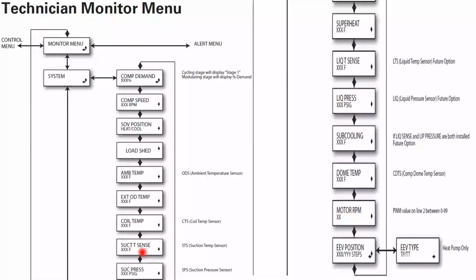We can see our suction T-sense, our suction pressure. So if you have your gauges hooked up, I like to compare that to what I have on my gauge. So keep that in mind. We have 110 on our suction pressure on our gauge. We should be right close to 110 on your suction pressure. We can see our superheat. We can see our liquid.